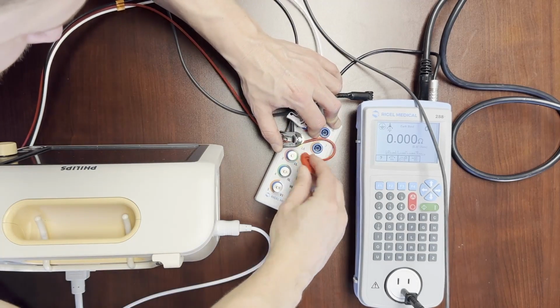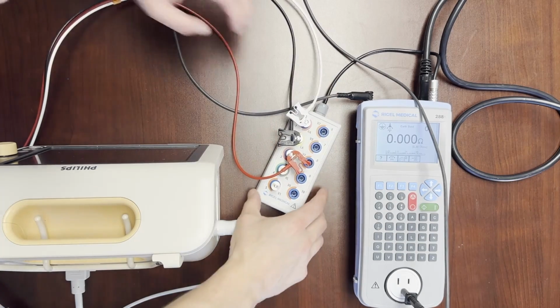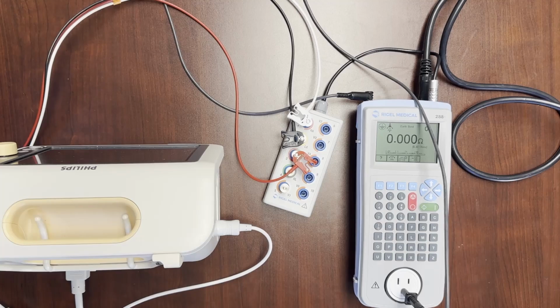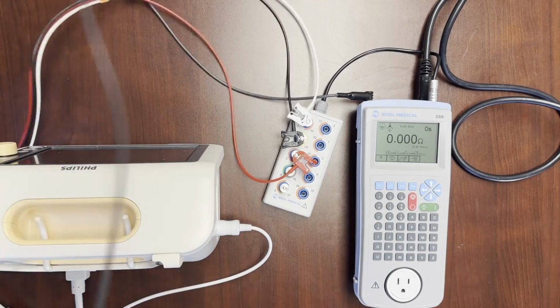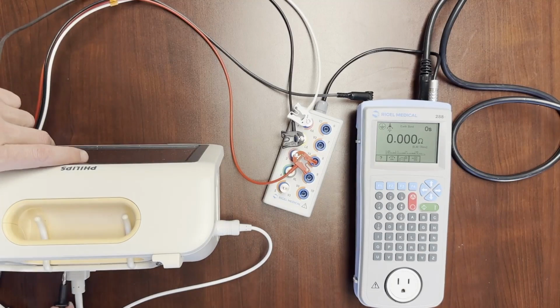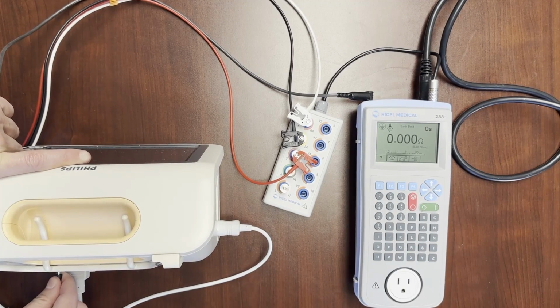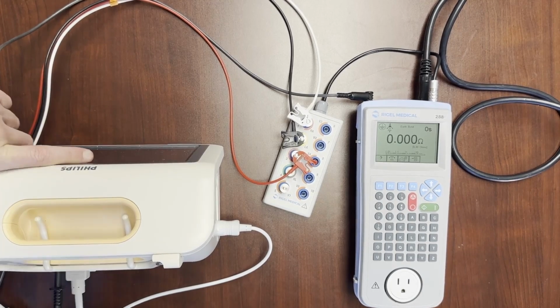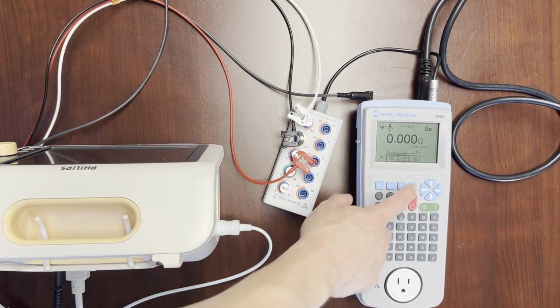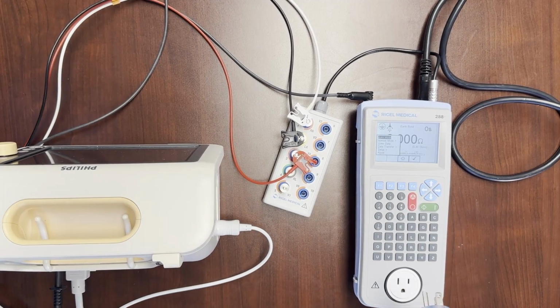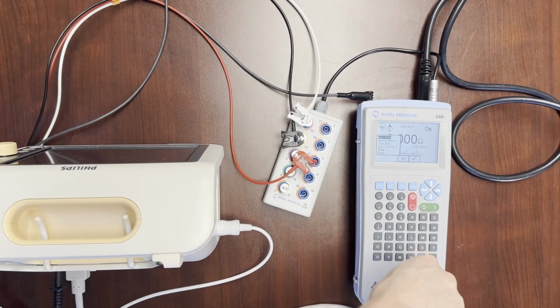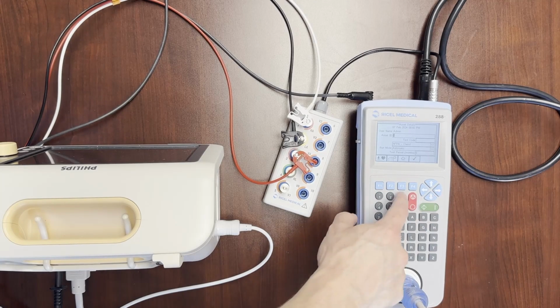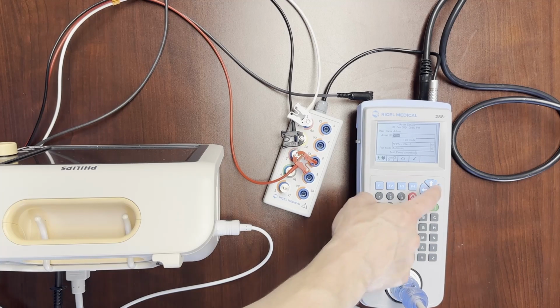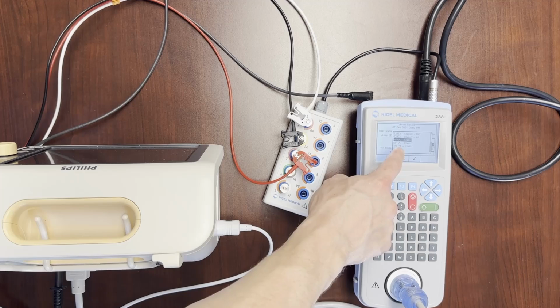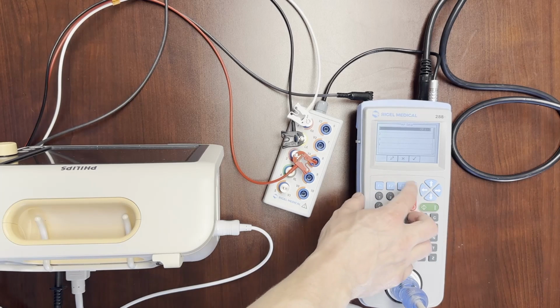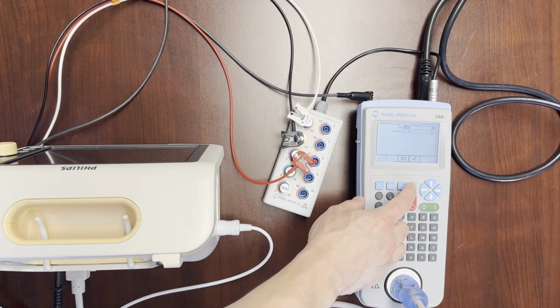Now this is a fully automated safety analyzer, so it can be done through the menu settings, select auto mode, and keying in asset information. It's fully automated, so we run the test sequence based on the NFPA 99 guidance for this type of device. As you can see, there's 10 applied part adapters, so just select automatic mode, plug in the device under test, key in an arbitrary number for asset details, check that we've got the correct standard for a class 1 device.